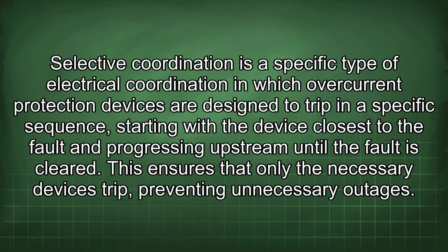operating. Selective coordination is a specific type of electrical coordination in which overcurrent protection devices are designed to trip in a specific sequence, starting with the device closest to the fault and progressing upstream until the fault is cleared. This ensures that only the necessary devices trip, preventing unnecessary outages.